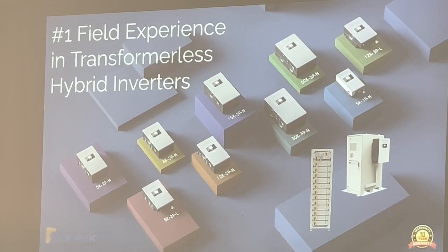The nice thing about the Sol-Ark inverter is you can just go right to the settings and adjust. Like I said last night, I switched this inverter from 208, 2 phases of 208, to split phase 240, which is what's coming out of this. You can switch it between 60 hertz and 50 hertz, and between having 1 pole at 240 or 2 poles at 120. So these inverters are switchable, but keep in mind if you buy a single phase inverter, it might be built for that market and the hardware might be different.